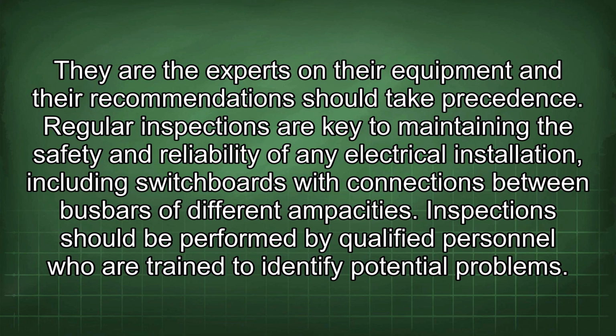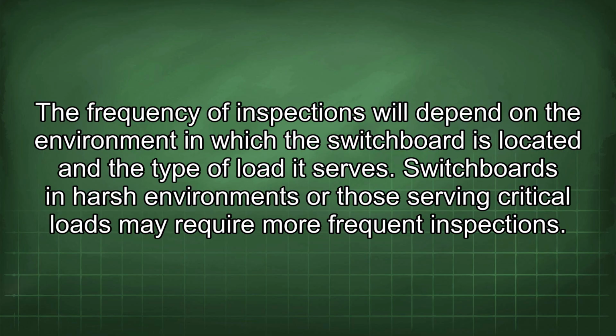Regular inspections are key to maintaining the safety and reliability of any electrical installation, including switchboards with connections between busbars of different ampacities. Inspections should be performed by qualified personnel who are trained to identify potential problems. The frequency of inspections will depend on the environment in which the switchboard is located and the type of load it serves. Switchboards in harsh environments or those serving critical loads may require more frequent inspections.